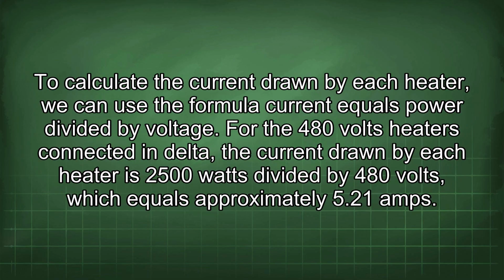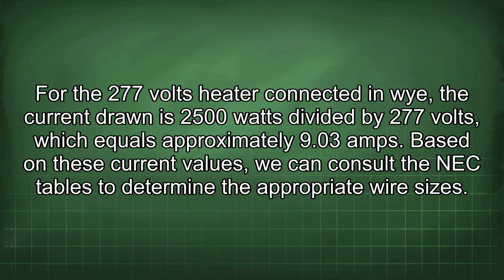To calculate the current drawn by each heater, we can use the formula current equals power divided by voltage. For the 480 volt heaters connected in Delta, the current drawn by each heater is 2500 watts divided by 480 volts, which equals approximately 5.21 amps. For the 277 volt heater connected in Y, the current drawn is 2500 watts divided by 277 volts, which equals approximately 9.03 amps. Based on these current values, we can consult the NEC tables to determine the appropriate wire sizes.